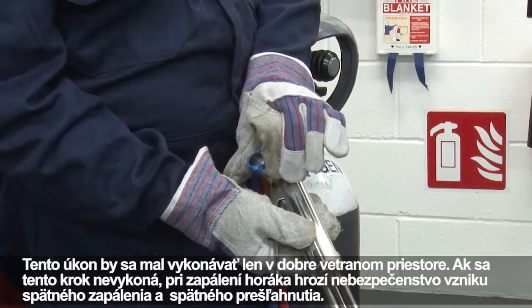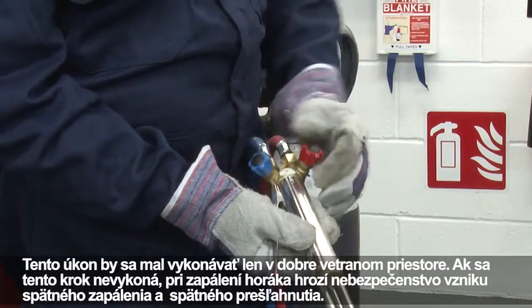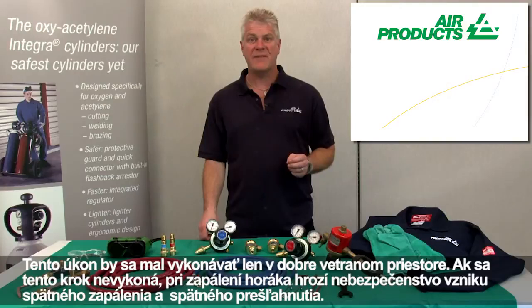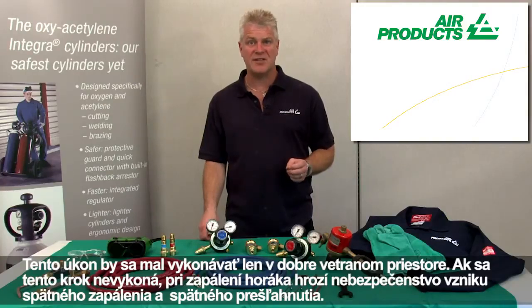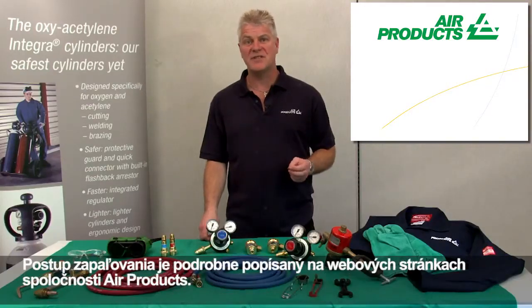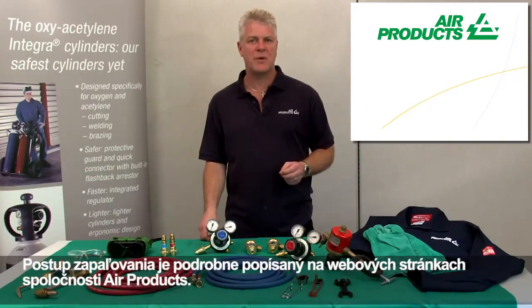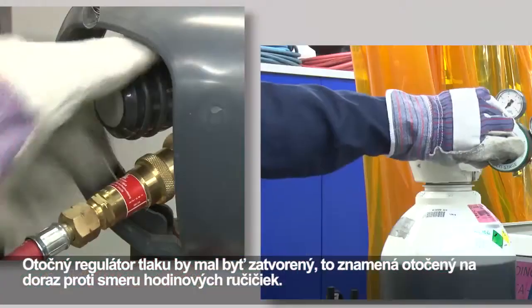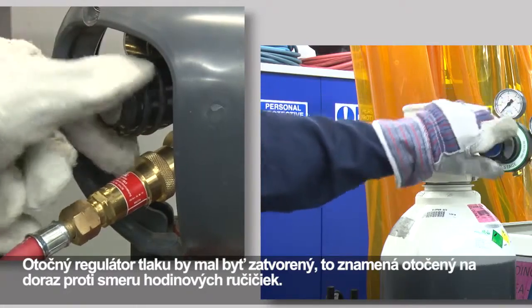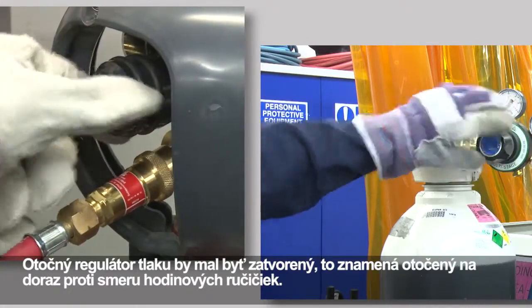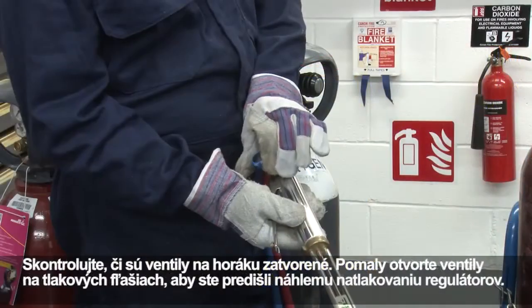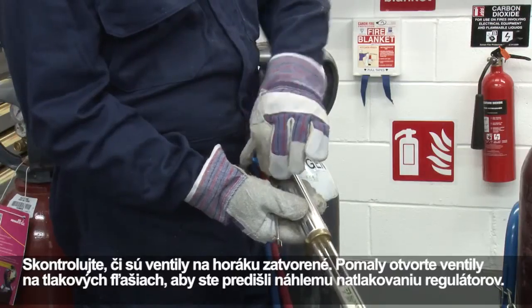This operation should only be carried out in a well-ventilated space. If this step is not carried out, there's a danger of flashbacks and backfires when lighting the torch. The lighting up procedure is described in detail on the Air Products website. The regulator pressure control knob should be closed. That's in the fully anti-clockwise position. Check that the torch valves are closed.